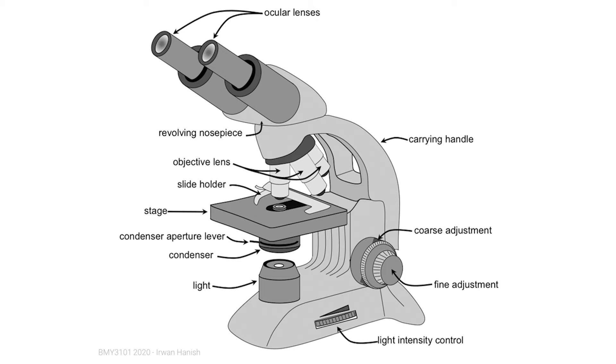Now, the objective lens. You typically have four objective lenses on your microscope. To correct the viewing focus, you adjust the distance between the objective lens and the stage. You do this by using two knobs. These two knobs are at the sides of your microscope. There is the coarse adjustment knob, which you use to make major repositioning. You then can fine-tune the focusing using the smaller knob. It's called the fine adjustment knob. So you play around with this until you get a sharp focus.